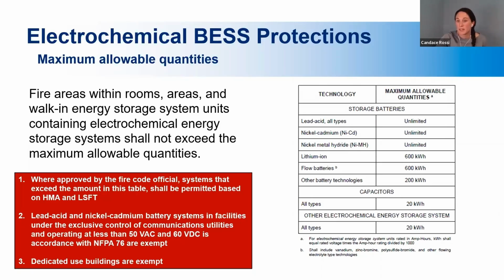Over in the table on the right, you'll see lithium-ion batteries in the middle showing a maximum allowable quantity of 600 kilowatt hours. You'll see that this is kind of where the tier 2 threshold comes from: basically anything over 600 kilowatt hours will have to meet all of these requirements.